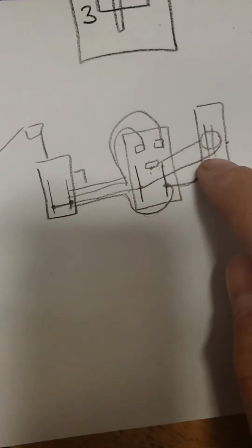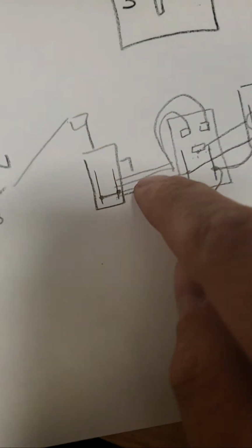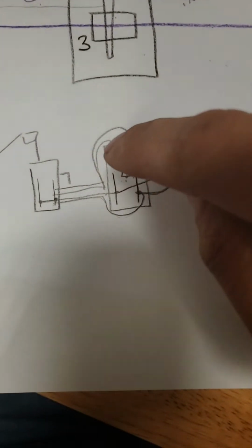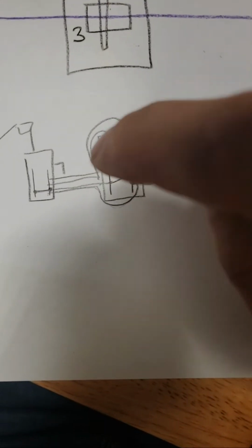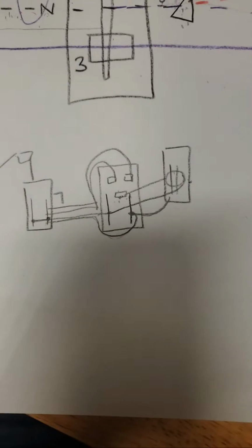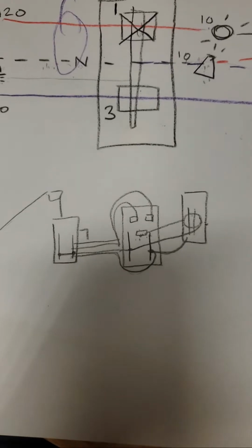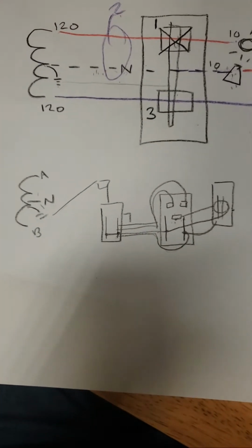Nice. Three-phase doesn't need neutral technically. Three-phase loads don't. Three-phase power does, because just like I showed you at this detail, you still got to get current back to the source. So without the neutral, can't get it. I was doing a temporary inspection for a crane, and they didn't pull a neutral to the transformer, and they didn't have a neutral in the main disconnect. And I flat out asked the guy, hey, I got a really stupid question for you.